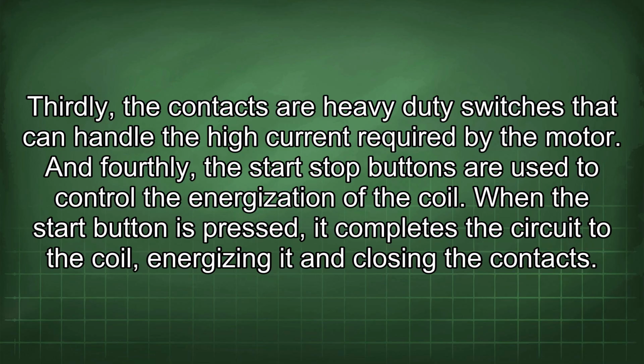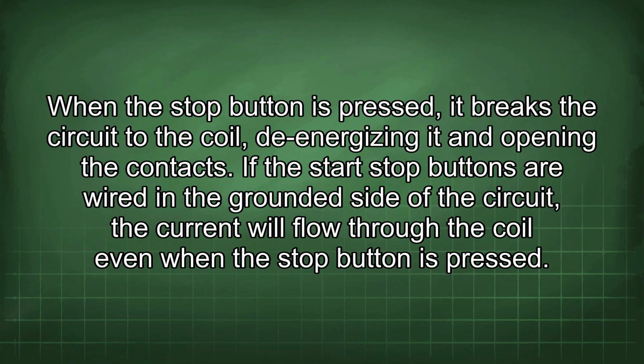Thirdly, the contacts are heavy-duty switches that can handle the high current required by the motor. And fourthly, the start-stop buttons are used to control the energization of the coil. When the start button is pressed, it completes the circuit to the coil, energizing it and closing the contacts. When the stop button is pressed, it breaks the circuit to the coil, de-energizing it and opening the contacts.